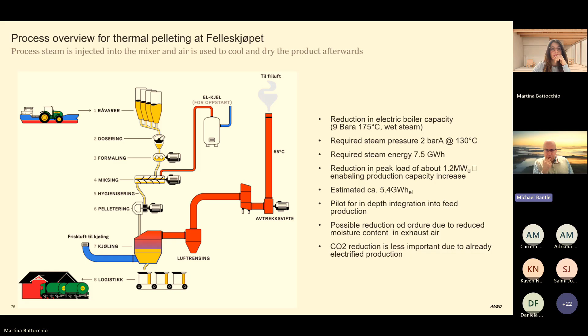This is on the next slide, where we have installed the energy recovery unit after the air filtration. At this point, the air has a humidity of around 35–40%, depending on the recipes, and a temperature of 65 to 75 degrees Celsius. Then we start cooling it down, and need to cool it down so far that we can actually get 1.2 megawatt out. That means that the temperature drops to around 35 degrees, or even lower maybe, depending on the recipe.